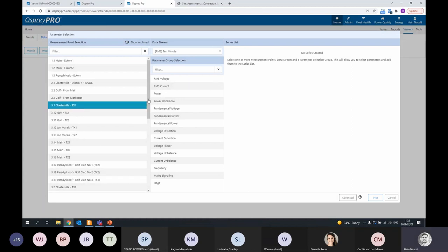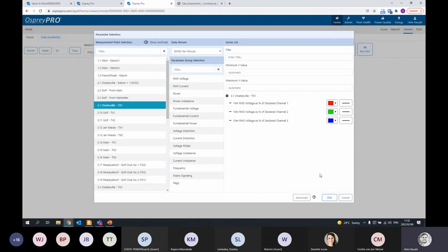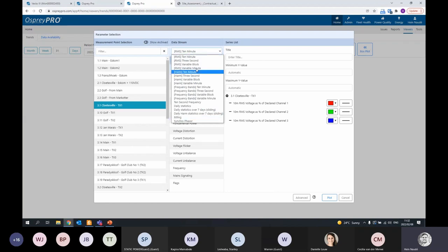I'm just going to select a random point, and you select the meter, you select what data stream you want to view. In this case, I want to view the 10-minute RMS data, but if you record a 3-second data, or imported it, you can view that, or the 1-minute data. And then we also have the harmonic, so it's categorized on the type of data you want to view. This is all RMS, and this is all harmonic channels. So you can view your 10-minute harmonic channels for the third harmonic, for example.